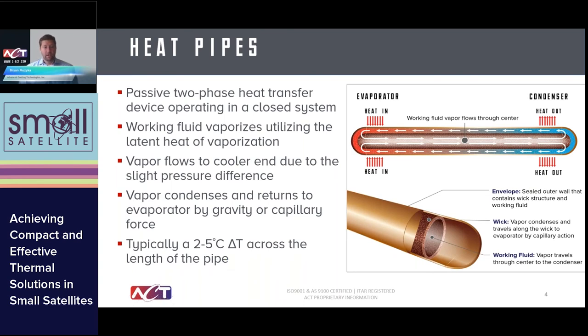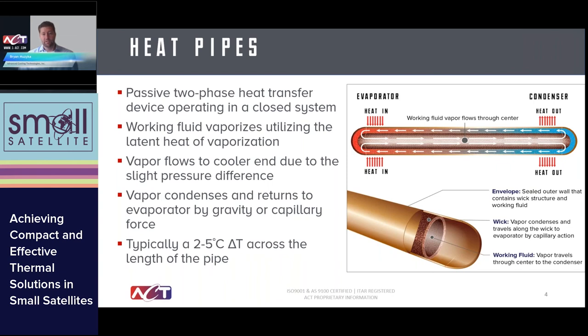Jumping into heat pipes — for those who know how they operate, we'll briefly touch on the theory and then talk about space considerations. A heat pipe is a two-phase liquid and vapor heat transfer device. Heat is input to one area, typically one end, which boils a fluid inside the pipe. That creates a pressure gradient that drives the vapor to wherever it's colder in the system, where it condenses back to a liquid and gets absorbed by the internal wick structure lining the ID of the pipe. The wick passively uses capillary action to pump the fluid back to the heat input zone. It's a passive solution with no moving parts and no active pumping capability, providing very efficient heat transport based on two-phase principles.